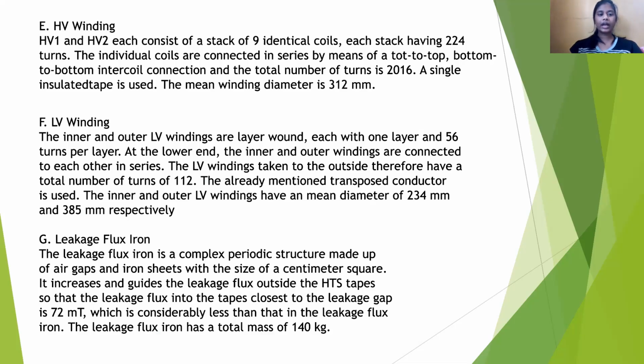LV winding. The inner and outer LV windings are layer wound, each with one layer and 56 turns per layer. At the end, the inner and outer windings are connected to each other in series. The LV windings taken to the outside, therefore, have a total number of turns of 112. The already mentioned transposed conductor is used. The inner and outer LV windings have a mean diameter of 234 mm and 385 mm respectively.